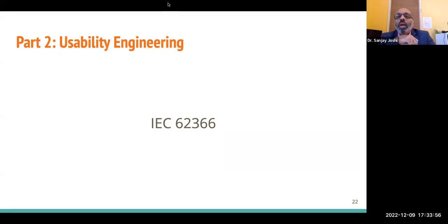Well, it depends. When you tweak something, are you going to sell it as a completely different device, or is that the same device with a design change? There is something called a design change for this product, and there you have to do a lot less work if it's a change to your existing device. For any change, you have to document the impact of that change. Almost always the question comes up: what is the impact on the risk? You typically go through a design change process to implement the change. Many times you end up revising your existing design history file, your risk analysis, requirements, and verification, but you typically don't create new documents for that.